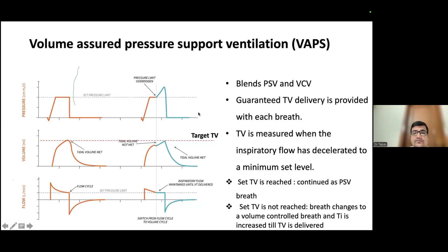Okay, so it is a much more refined form of ventilation as compared to PRVC and VG, because here adjustment is happening in a particular breath itself and not over the subsequent breaths. Okay, so guaranteed tidal volume is delivered with each breath. As I've said, if the set tidal volume is reached, it will continue as a PSV breath. However, if the set tidal volume is not reached, the breath changes to a volume control breath and TI is increased until the tidal volume is delivered. So remember that this mode of ventilation will only work in babies who are spontaneously breathing.